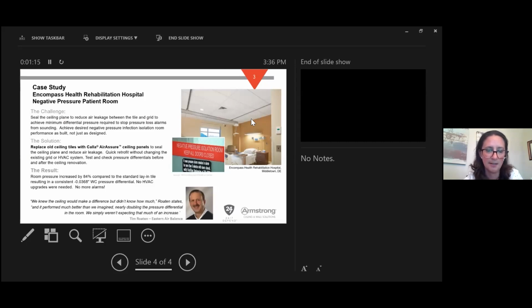It is a ceiling tile that will improve pressurization by reducing the leakage through the ceiling plane. This is an isolation space in a hospital in Delaware. The client was having a difficult time maintaining pressurization. They consulted with their air balancer, and the air balancer suggested that before they go through significant changes and retrofits to their ductwork or exhaust fans or additional costly changes...